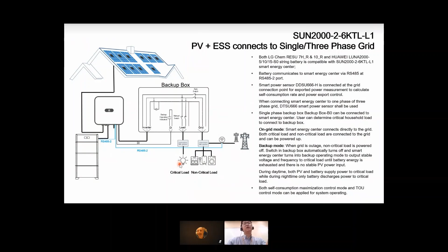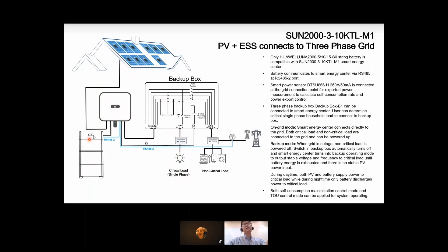For the three-phase backup, emergency power supply, the battery model is only Huawei's Luna 2000. LG does not work here. When the grid is on, both the critical loads and non-critical loads work normally. But if the grid power is down, similarly, the auto switch here will disconnect and the manual switch here will be connected. So you will get power for the critical loads, and both PV and battery will provide power. The priority is PV first, battery second.